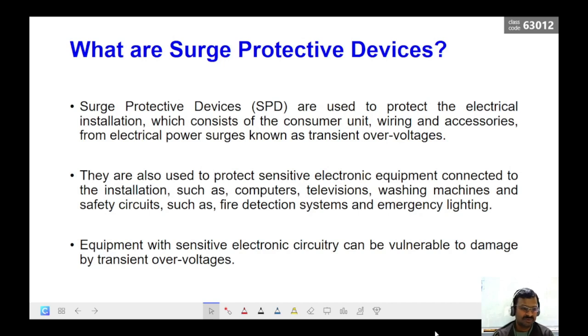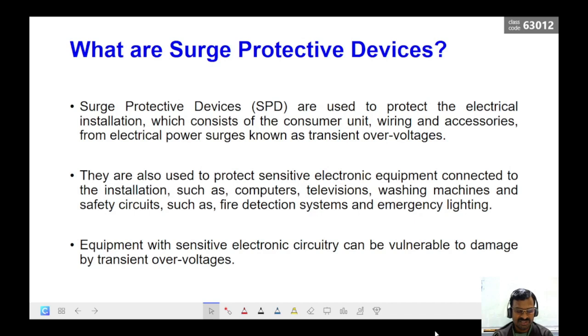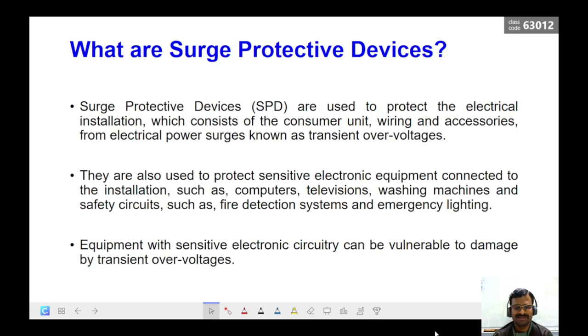Which part of the electrical power system are you going to protect? It may be in the transmission, or it might be in the distribution, or it might be in the consumer side. Based on this, the voltage levels and the current levels are going to be different, and based on that you are going to have different mechanisms and different types of SPDs. On the load side or consumer side, you may have very sensitive electronic devices or very costly devices which need to operate uninterruptedly, so these devices have to be given protection at most points.